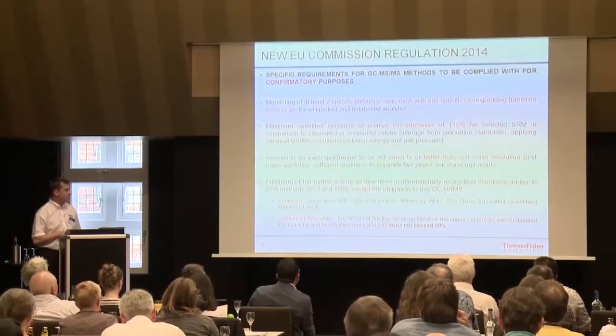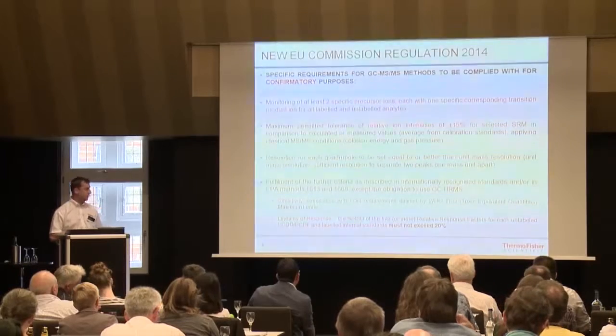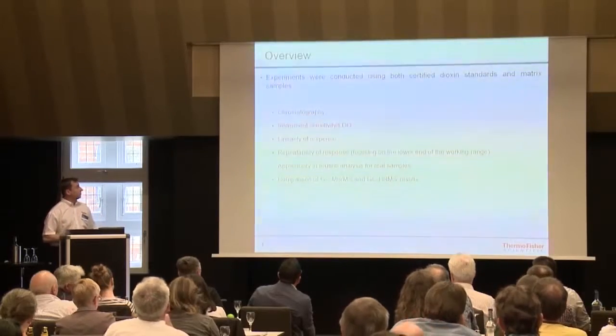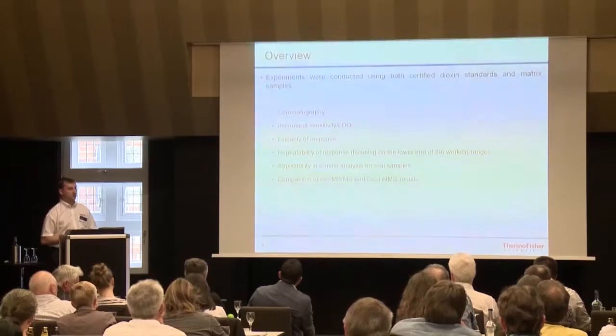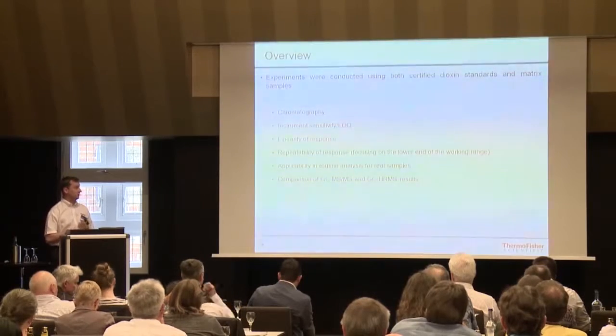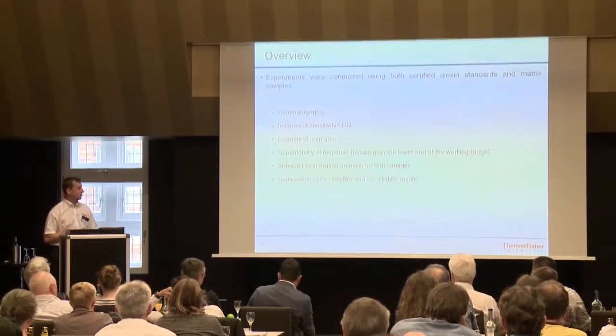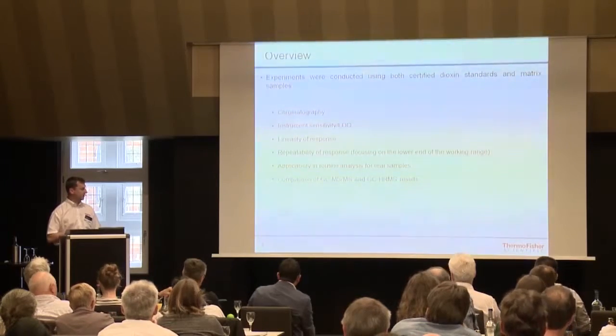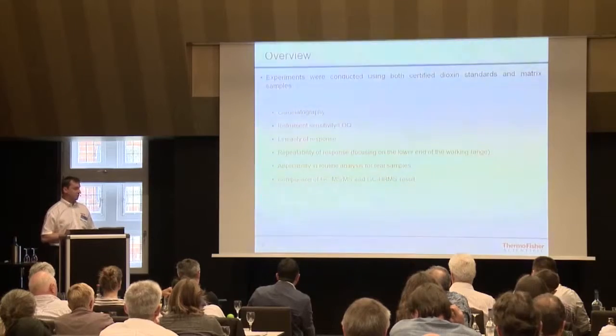This is an example of the sensitivity compliance and linearity of response, which refers to the percentage RSDs that should not exceed 20% across the calibration curve. What you'll see next are examples of chromatography, instrument sensitivity expressed as limit of quantitation, linearity of response, repeatability of an injected standard and samples, matrix samples, and also routine analysis of real samples and direct comparison of GC-MS/MS results with GC high-resolution mass spec for the same set of samples.